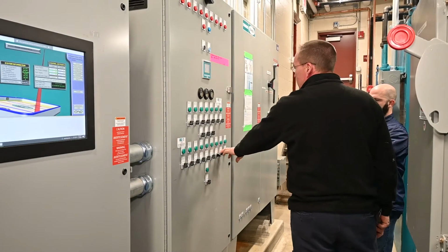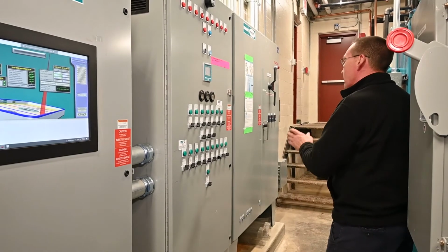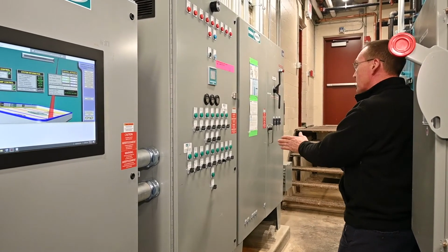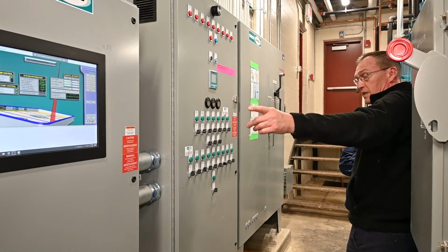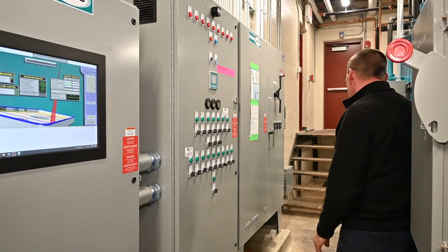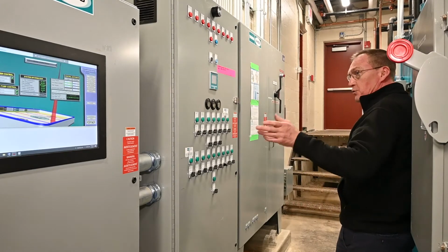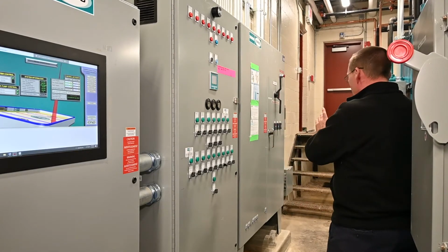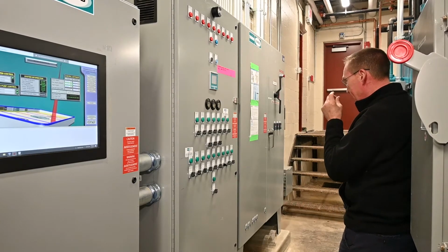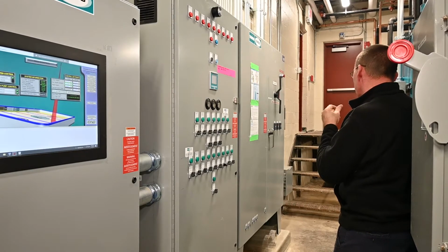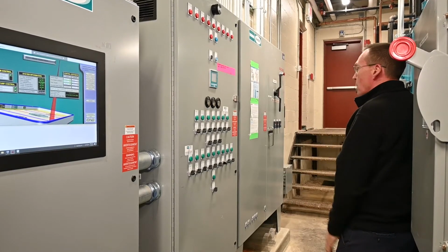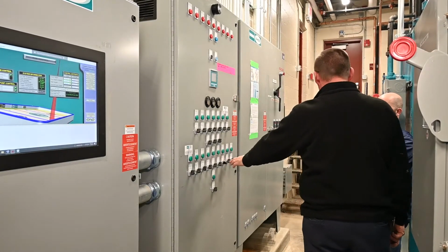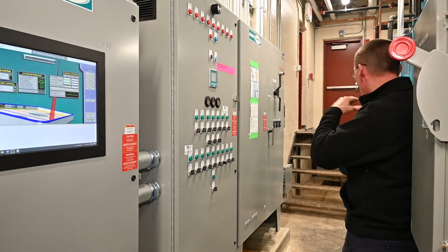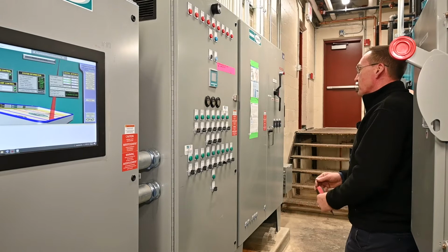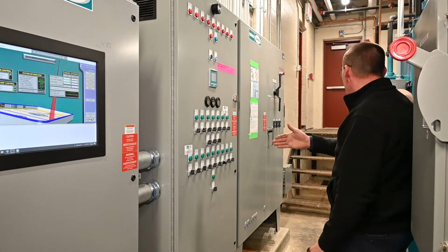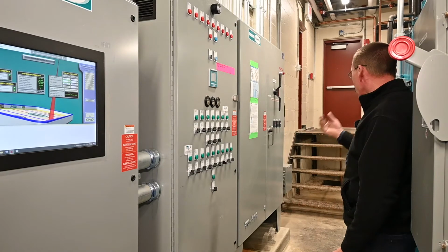Cooling tower fan. Okay, there's two variations of how that fan outside can be run. One is in VFD, which we'll go over in a minute, which is that first VFD there, or it can be run in bypass. Bypass is the computer tells it to start and stop, and there's a contactor in the main panel that will spin the fan up to 100% speed as if it was a normal mechanically controlled fan. Whereas the computer likes it to be in VFD because we can then vary the speed of that fan and only use the power that we need to. But if there is a problem with the VFD, then it can go into bypass and the computer will take over starting and stopping the fan.